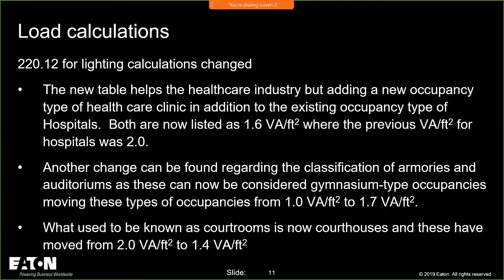Now, 220.12, again, the new table helps the healthcare industry, by adding a new occupancy type of healthcare clinic. What we did was we created a healthcare clinic, which wasn't there before, and that's at 1.6 VA per square foot. If you looked at hospitals, they went from 2 VA per square foot down to 1.6. So we lowered the VA per square foot for a hospital.